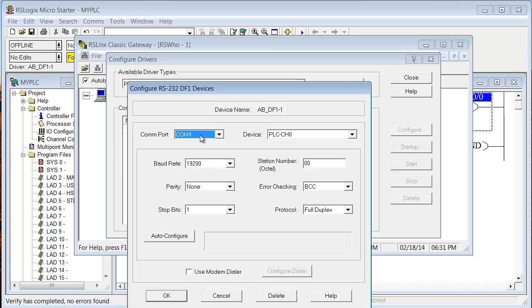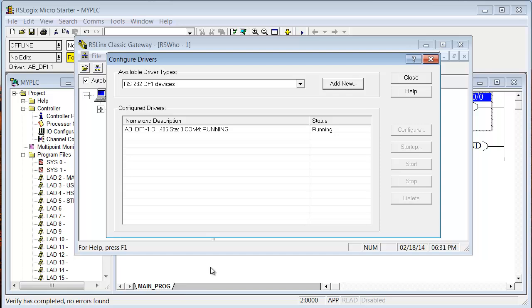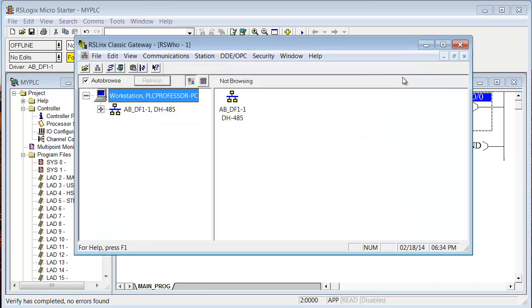So we'll close that back down. We'll pick 4. So we're saying, we're telling RSLynx, we want you to auto-configure, and we want you to go to COM4, which has been assigned to that USB port. So we click on Auto-Configure, you see it's trying all kinds of iterations until it finds something, meaning it sends out a message at all these different baud rates, error checking, configurations, stop bits, parity, etc. If it doesn't hear anything back within milliseconds, it sends out another. When it hears something back, it knows that the configuration of the message that it sent out matches what's in the processor, so it says Auto-Configuration Successful. So we see it's at 9600, so I'm going to leave the driver set like this. So write Auto-Config Successful, click OK, and you're good to go. So I'm going to close that. Now, I'll close this again. We don't need that.